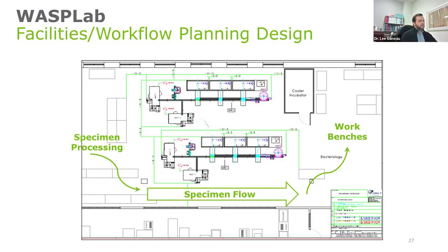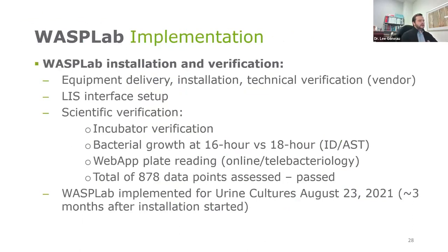This is just what our lab looks like. We have two WASP Lab lines, three double incubators, and four WASP pre-analytical modules. These are fed through the lines and offloaded to be taken to workbenches on the right-hand side. For installation and verification: LIS interface setup was a lot of work. Scientific verification — we looked at the incubators and verified a shorter incubation period because of optimal growth conditions, changing our cultures from 18 hours to 16 hours. We had to verify the performance of staff to do telebacteriology — looking at plates on a monitor rather than physically. The WASP Lab was fully implemented for urine cultures in August 2021, approximately three months after installation had started.